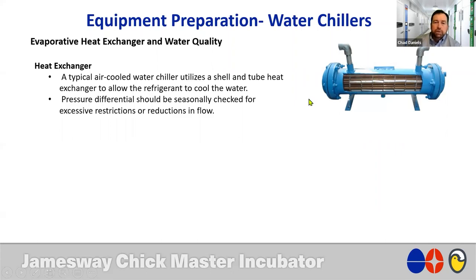The reason it's important to mention this again, if I have an issue with my heat exchanger, I want to make sure I get that taken care of during the season when I can shut it down and I don't have to worry about being without it. So even though you may be entering winter and you need heat, you want to be able to do that repair off season. And a way to check that on a chiller is we look at pressure differential on the water flow through a shell and tube heat exchanger.